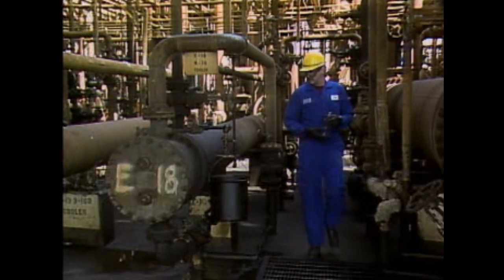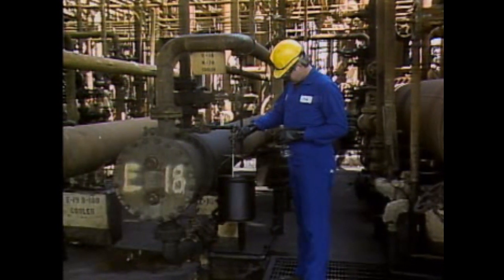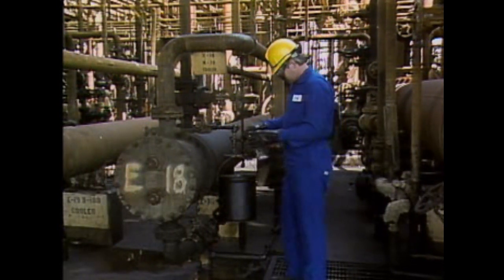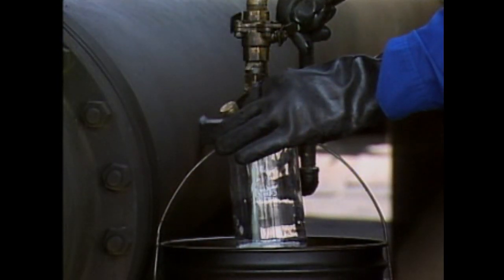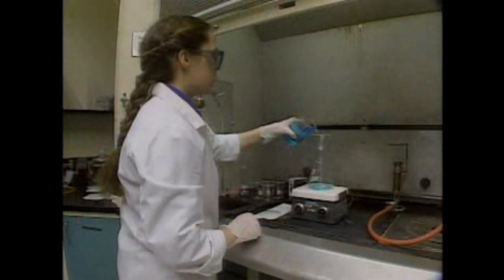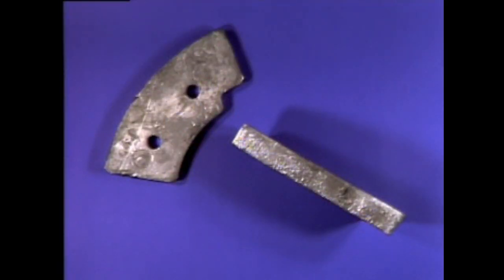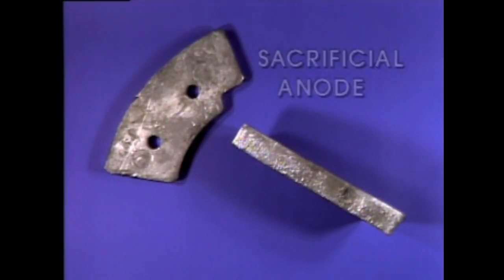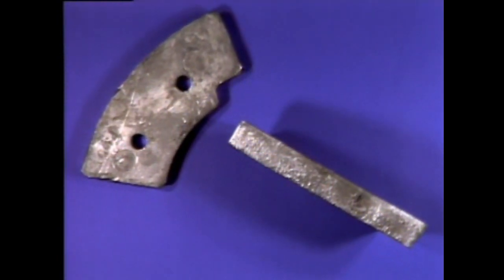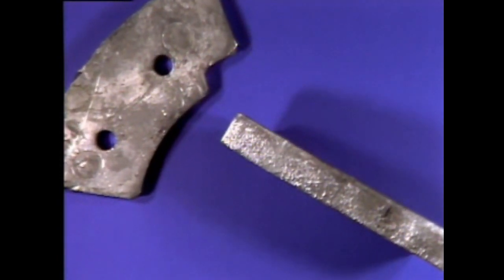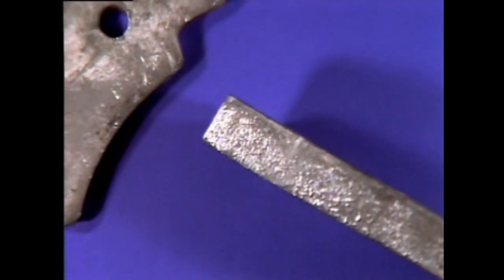One way to check for tube leaks is to take and analyze a sample of the lower pressure fluid. When a leak occurs, the high pressure fluid leaks into the low pressure fluid. In some cases, you may be able to tell there's a leak by just looking at the sample; in other cases, a lab test may be required. To prevent leaks in some applications, the process fluids pass through filters or strainers to remove impurities that can erode the tube metal. Also, chemicals may be added to the fluids to control corrosion. Another method of controlling corrosion involves using a device called a sacrificial anode.